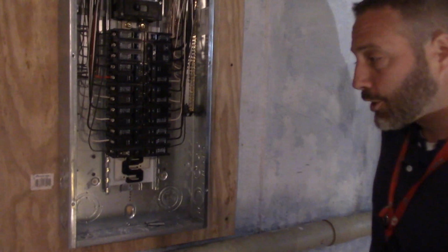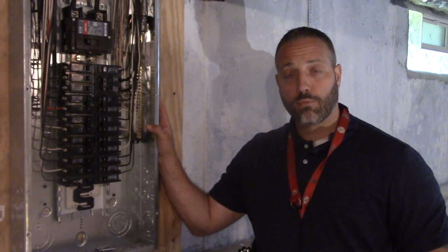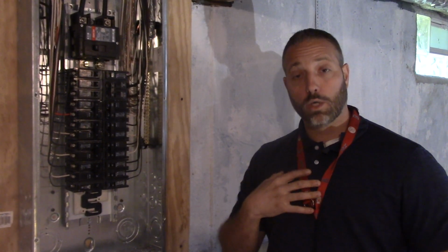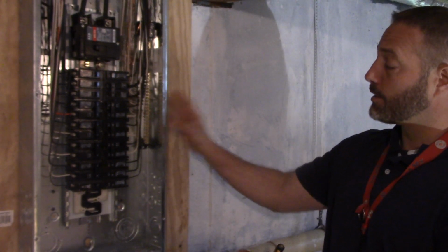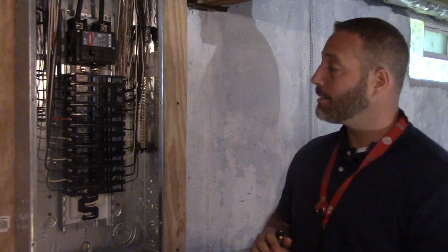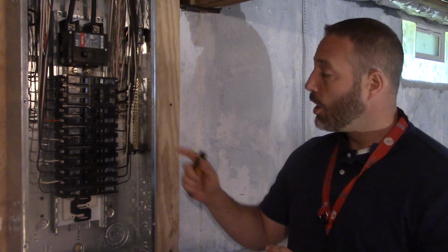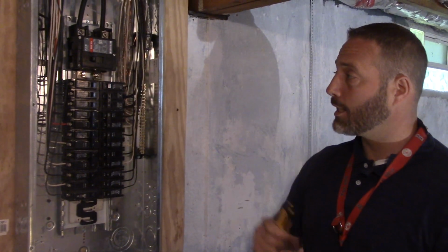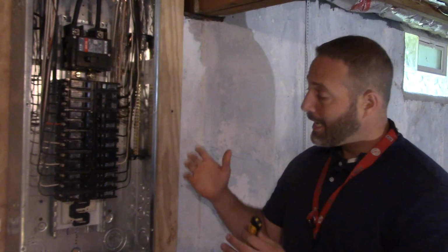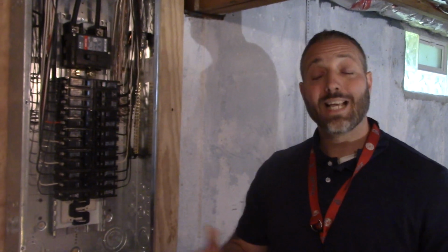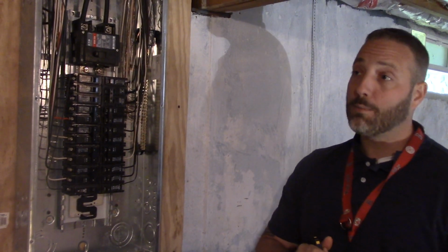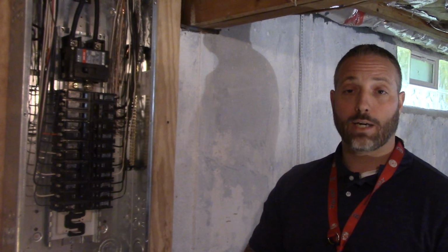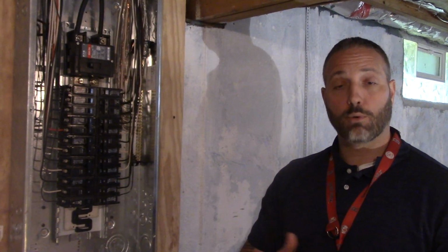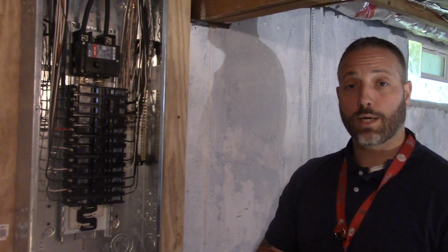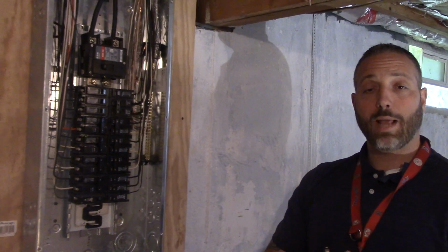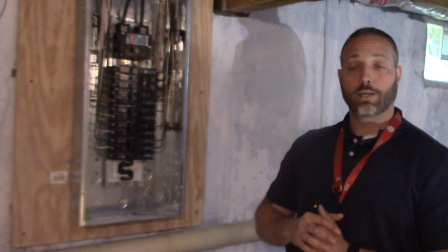So when it comes to an electrical panel, this is a critical item for performing a home inspection. One, we want to make sure we're in a safe condition to perform this electrical inspection. But two, we want to make sure that we have the proper wire sizes with the appropriate breakers. We want to understand what the main breaker size is, just in case it is smaller, for example, a 60 amp breaker. In today's condition, that is pretty much a limited electrical main panel, and we're probably going to request an upgrade to at least 150 or to a 200 amp breaker. So this is how you perform an electrical inspection on a main electrical panel.